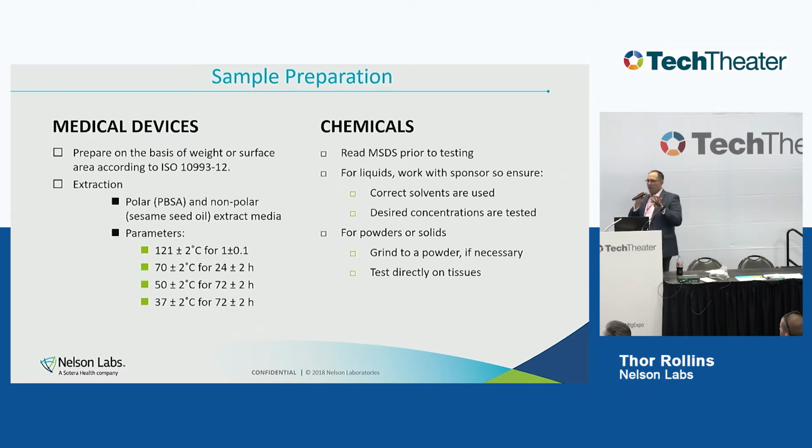But when you look at the difference between the chemical test and the medical device test, really what the difference with the medical device is the extraction procedure. We wanted to make sure that the medical device extraction that is in -12 would work for this test. In fact, when we ran the validation for this test, this was mostly what the validation was, because we knew the test already worked.